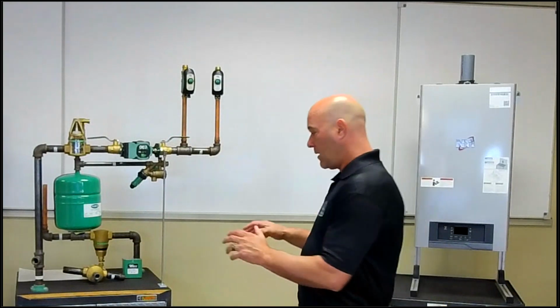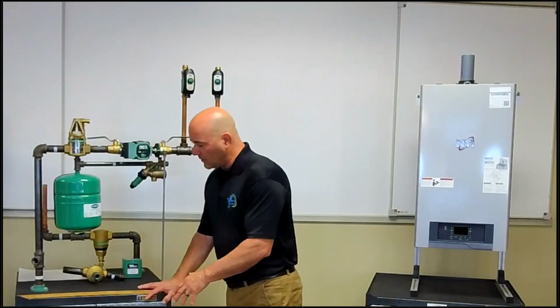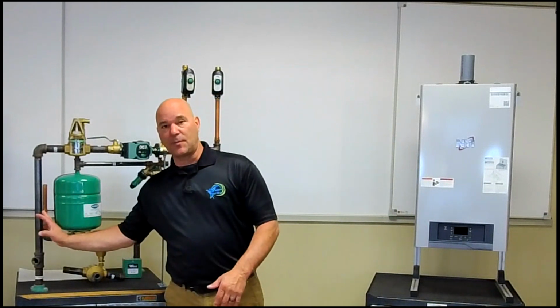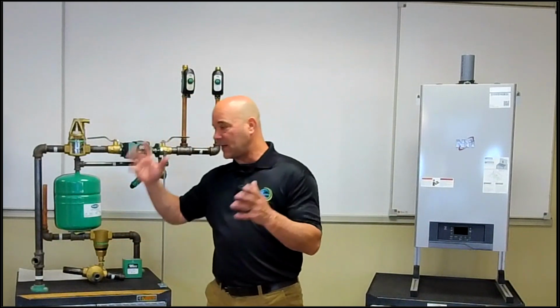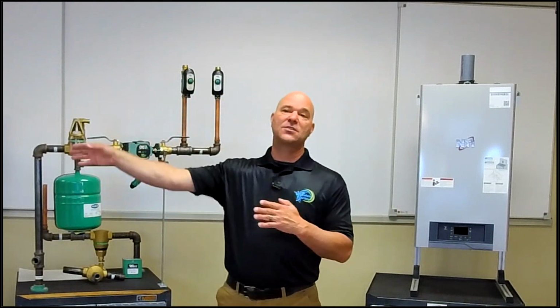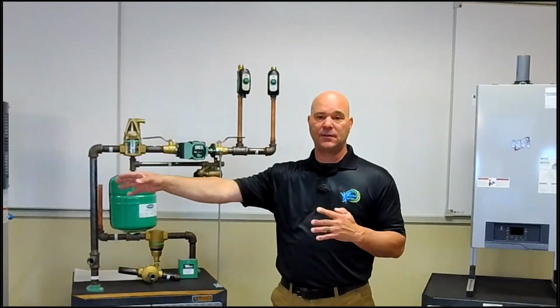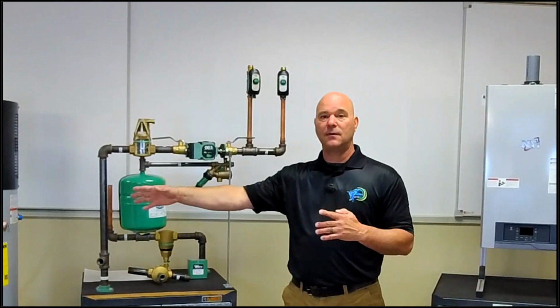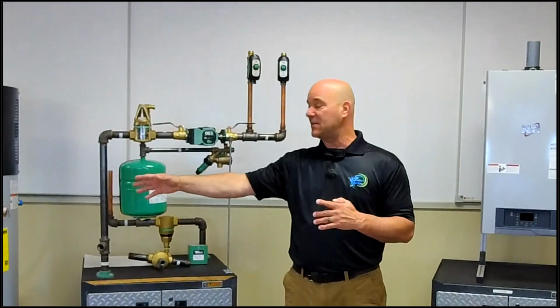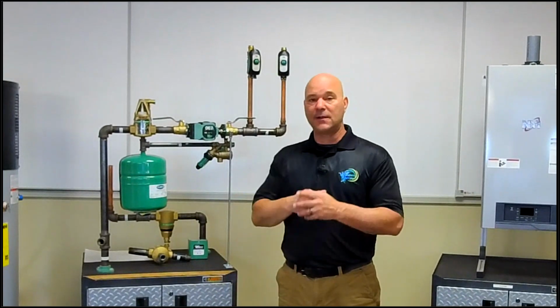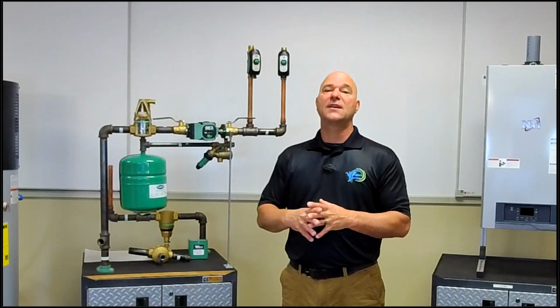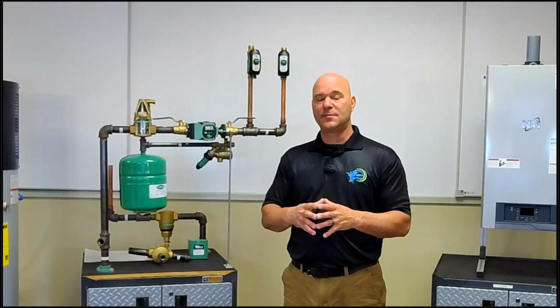So I know this is only a 100,000 BTU boiler. Let's say I'm on 1.25-inch pipe or 1-inch pipe, I'm right on the edge. I have to have a circulator on there that has the ability to deliver that flow rate of 10 GPM to that indirect, and that indirect has a coil inside of it that has the ability to absorb that 100,000 BTU and will exchange that energy, and that would take 11.7 minutes, right?